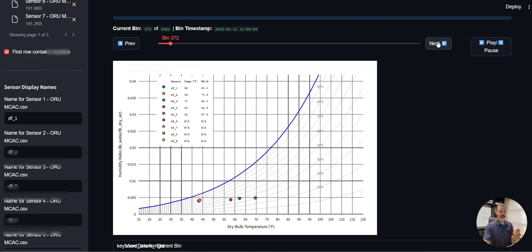And at this point, you're condensing on the bottom of your roof, and it's creating moisture. It's saturating the insulation from the top side and dripping onto the gymnasium floor. So issues there, but you can just pull around and learn a few things like that. I think it was around here.